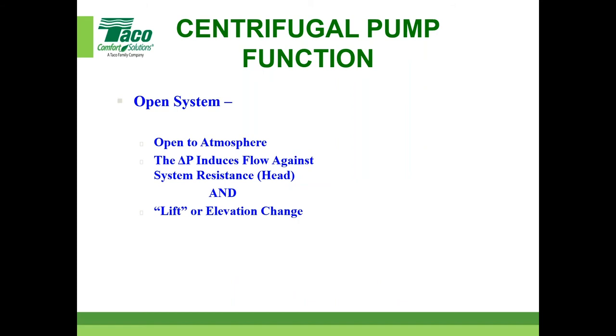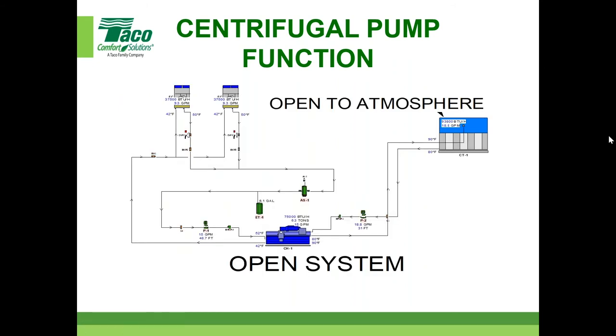Open system, open to atmosphere, like I've already mentioned, there is some head for lift or elevation change, okay? So that has to be included in your calculations. On the right-hand side here, this is my open system, open to atmosphere. That's supposed to be an arrow; I kind of cut it off a little bit. So that elevation change from here to here needs to be included in your calculation, not just the piping and the elbows and the fittings and the valving and everything like that and the chiller barrel. Nonetheless, we like to clarify that because every once in a while someone asks us that. It's just a basic premise that needs to be taken into account and understood.